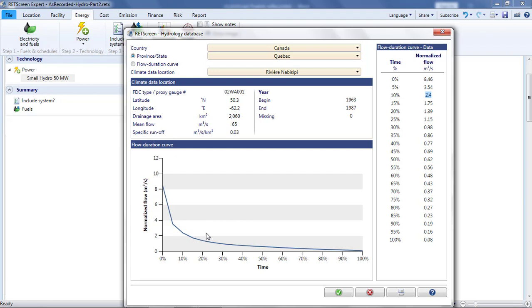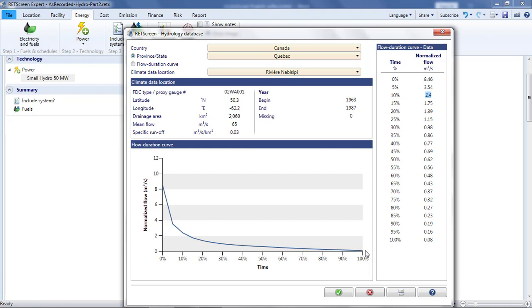A flow duration curve is an essential element of a hydro resource assessment. Ideally, it will be produced from a long-term series of regular measurements of the flow in the river. Where measurements are not available, the flow duration curve may be based on estimates of the mean flow and the generalized shape of the curve as observed in rivers with similar characteristics. A variation of this approach, applicable to Canada, will be shown in part 4 of this video. For now, however, I will simply assume that I have been provided with the data for a flow duration curve. I'll have to enter this manually into RETScreen.